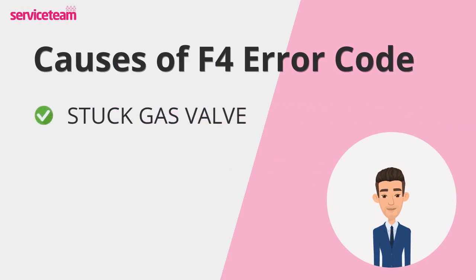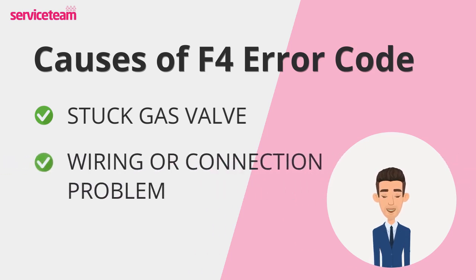First cause is a stuck gas valve. This little component controls the flow of gas into your boiler. If it gets stuck, gas won't reach the burner, and without gas, there's no flame, triggering the F4 fault. Next, wiring or connection problems. Your boiler depends on electrical signals to operate smoothly. Loose or damaged connections can disrupt these signals, especially the ones that tell the system if a flame is present.